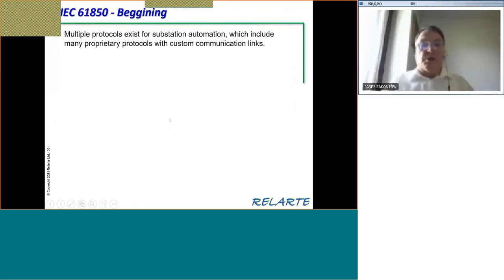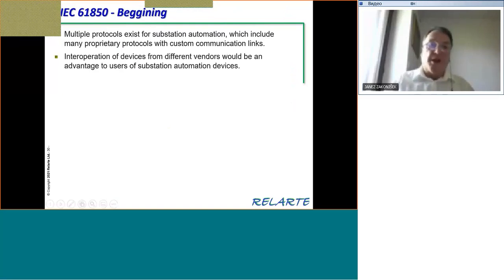So then we come to IEC 61850. We had been discussing very much about communications, about digital relays and electronic devices, which were using many different protocols. This was difficult for users because it was hard to make one common system in a substation. So it was necessary for vendors to agree on one common communication system, which would make development of substation automation devices and relay protection much easier.